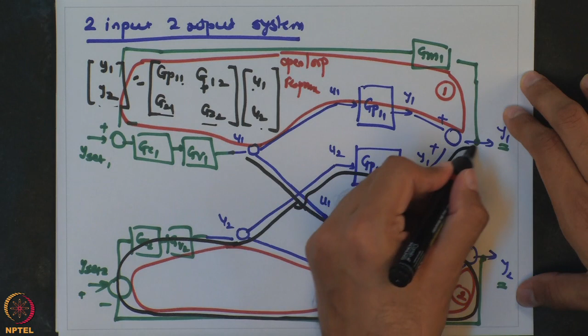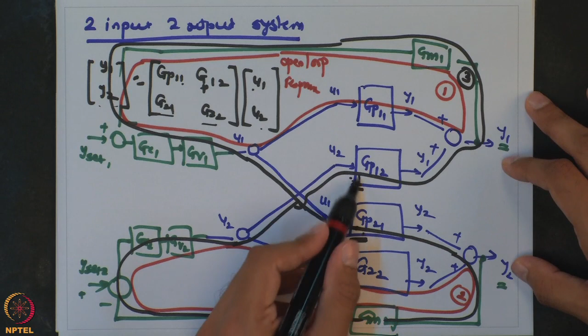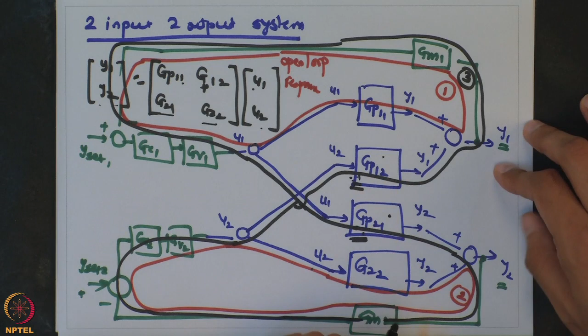So there is an additional, third loop which causes that interaction term, and this loop goes through the transfer functions Gp21 and Gp12. As long as you have these cross transfer functions, if any one of those transfer functions is non-zero, your two control loops will interact. Now note that this loop will not be formed if either this or this was equal to 0. So you don't necessarily need both these cross transfer functions to be there. Even if one of them is 0, you would not have this third loop, and then the interactions in the system will go to 0.